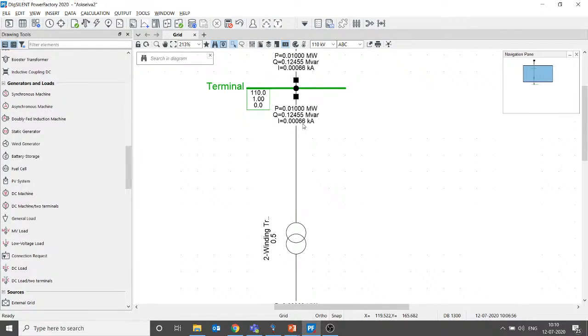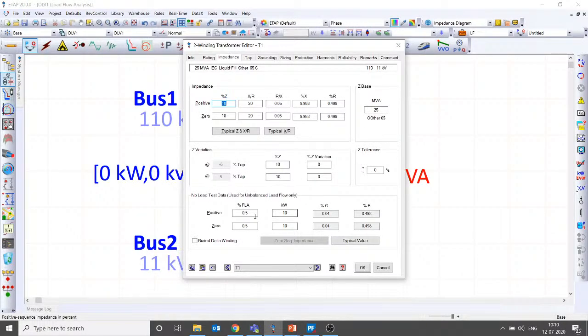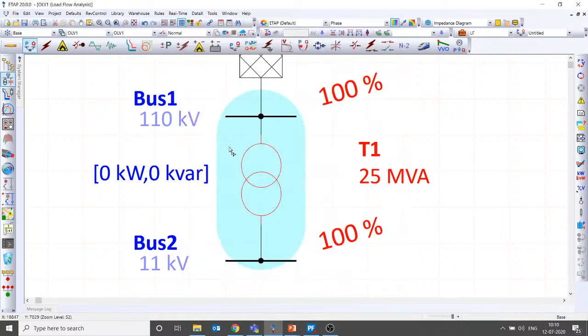Yes, so what is the loss which I have given? The loss is appearing here. That means DIgSILENT PowerFactory is accounting for this no load loss even in a balanced load flow. It is really the right approach. But ETAP is not accounting for this no load loss in a load flow analysis. That's not strictly right, but the no load loss is a very small quantity, so it can be neglected. That is the error you are tolerating when performing a load flow analysis in ETAP.